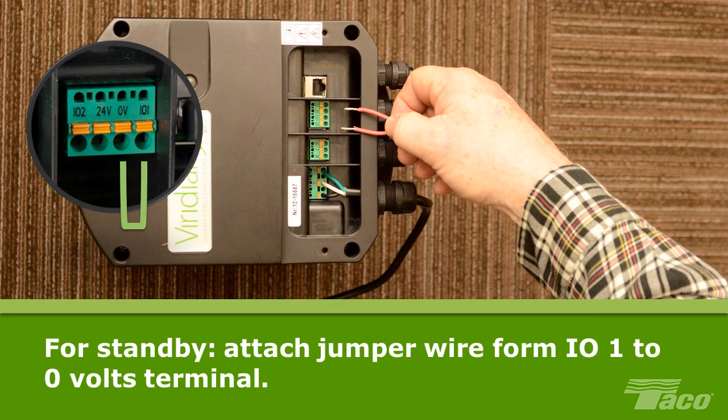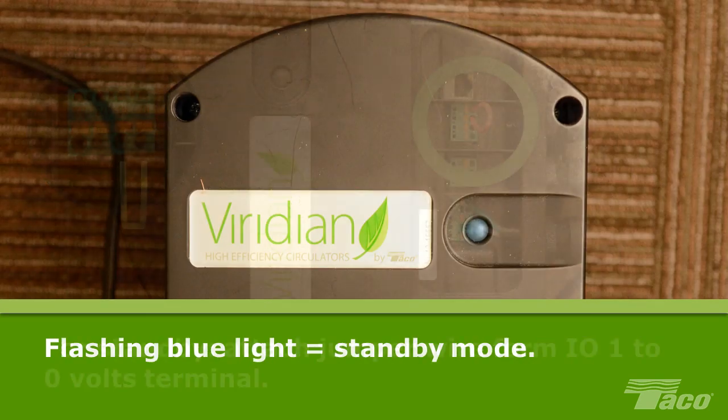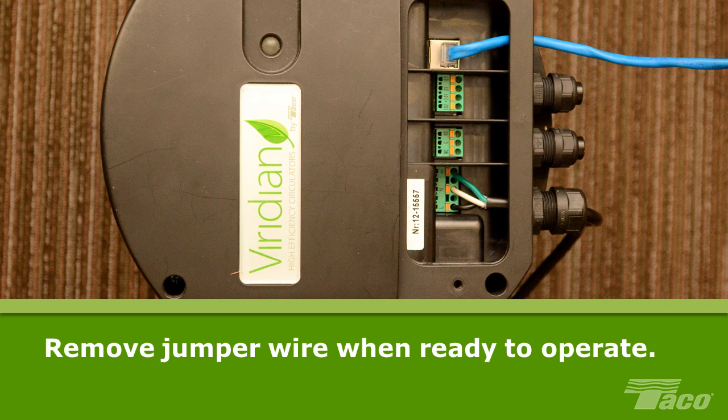To place Viridian in standby mode, attach a jumper wire from the IO1 terminal to the 0 volts terminal. A flashing blue light on top of the Viridian indicates that the pump is in standby mode. AC power can now be applied for programming. When you have completed programming through the Viridian interface, simply remove the jumper wire to begin operation of the pump.